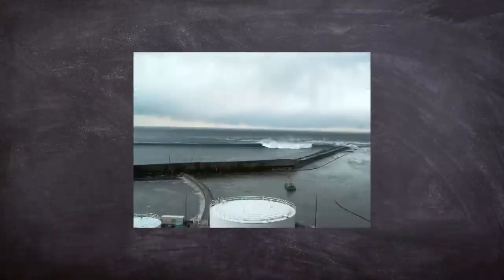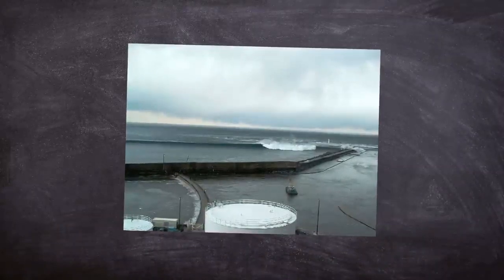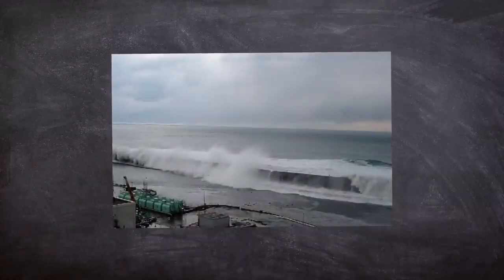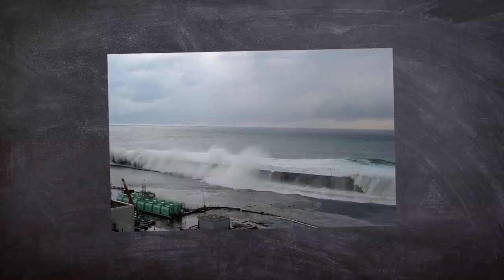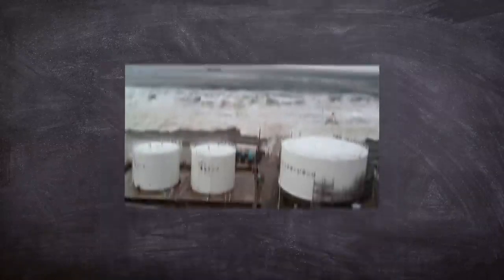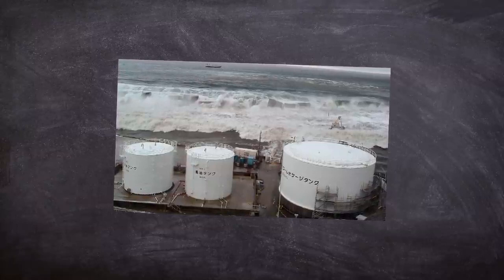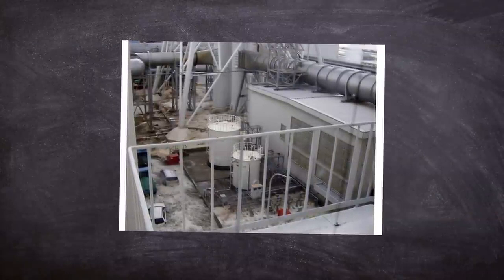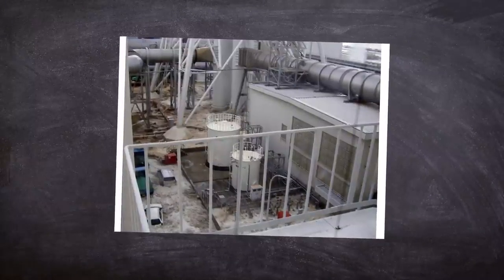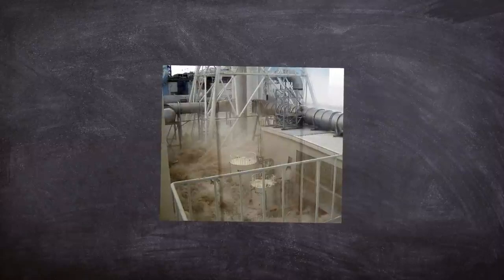However, 40 minutes post-seismic activity, the first tidal wave just under 5 metres tall crashed up against the sea wall which effectively protected the plant. However, just 10 minutes later, a second 14 metre high tsunami wave was heading for the power station. The wave effortlessly crashed over the sea wall which only provided protection of around 5 metres above the normal sea level. The water flooded the turbine rooms shorting out their electrical systems. The wave damaged the unhoused sea water pumps. This meant that essential plant systems that use sea water, including the liquid cooled emergency diesel generators, could not be cooled to ensure their effective operation.